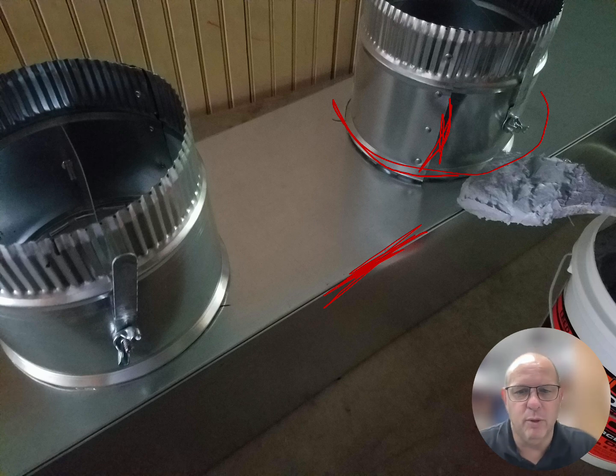Later on, I'm going to show you what we're going to do with that damper, because once we have adjusted the airflow to the appropriate airflow that's going into that room, we will take a screw and we will screw that damper in place, and that damper will never move from the location that we have placed it in there, providing for us the proper airflow and CFM into our branch runs for particular rooms that are out there.